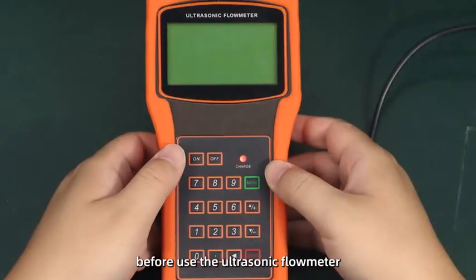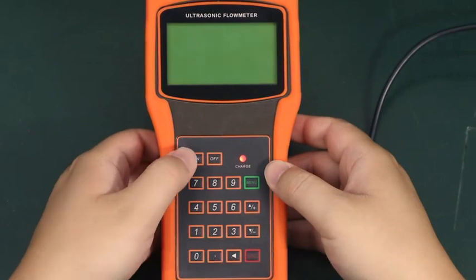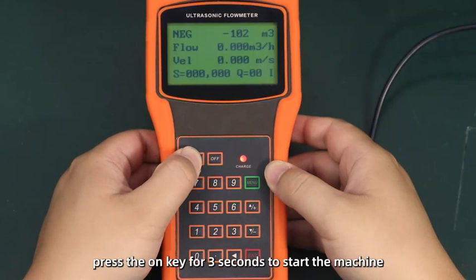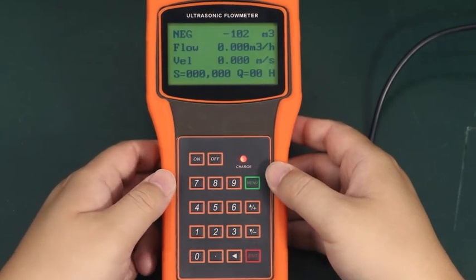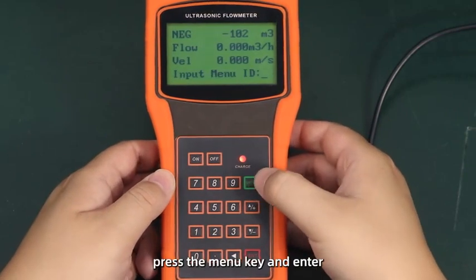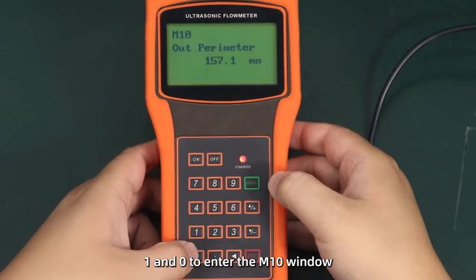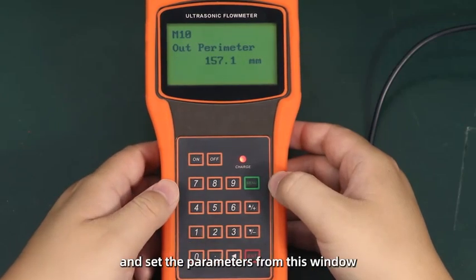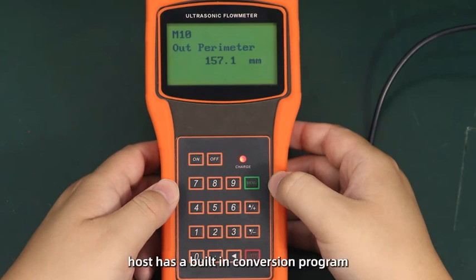Before use, the ultrasonic Flowmeter needs to accurately set the specific parameters of the on-site measured pipeline. Press the on key for 3 seconds to start the machine. Press the menu key and enter 1 and 0 to enter the M10 window, and set the parameters from this window. Because the Flowmeter host has a built-in conversion program, the pipeline perimeter of this window does not need to be changed, and the host will automatically convert and replace the data from the subsequent input parameters.